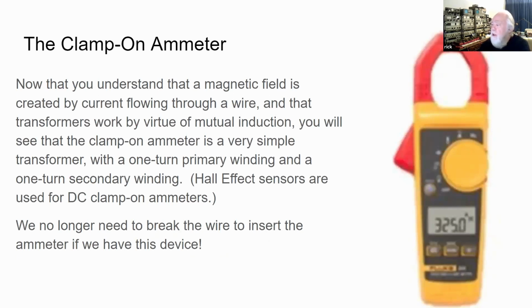Now, the Clamp-On Ammeter uses that same method of measurement, but the actual secondary winding in the transformer of the measuring device is this clamp-on jaw, which is opened by pushing this button. This jaw continues the path of current to make a single, one-turn winding of the secondary of the air core transformer, and the primary is just the wire from your battery to your circuit breaker. You can measure the current from your battery with this device without having to break the wire and put the meter in series.